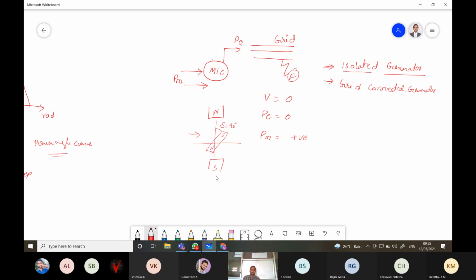So before delta reaches 90 degrees, we need to clear this fault by using the circuit breaker. The circuit breaker should operate, and how fast it operates maintains the stability. Before delta reaches 90 degrees, the circuit breaker should operate and it has to isolate the faulted system from the healthy system. So that is called your stability. So this is the critical clearing time.